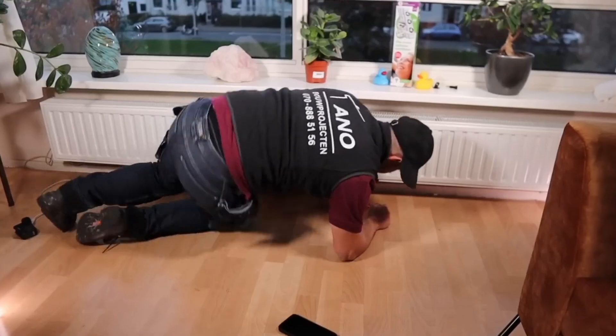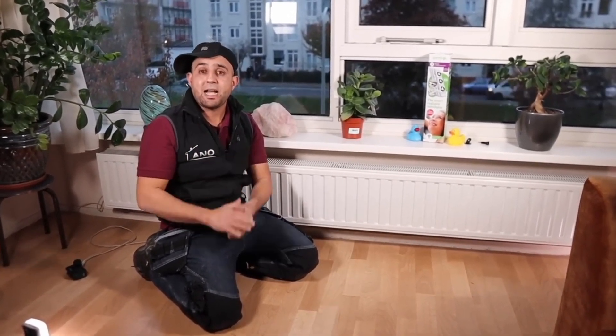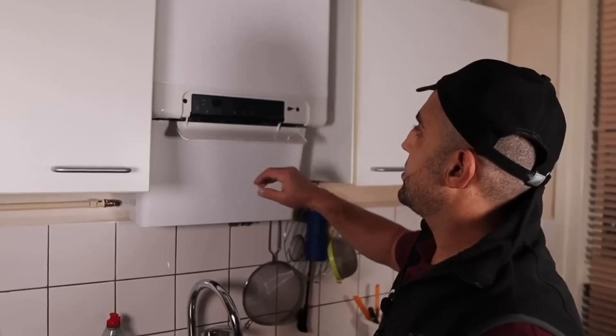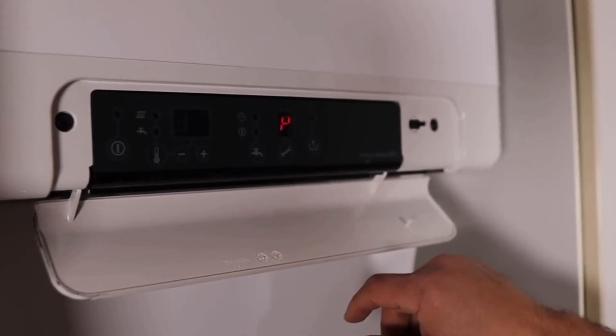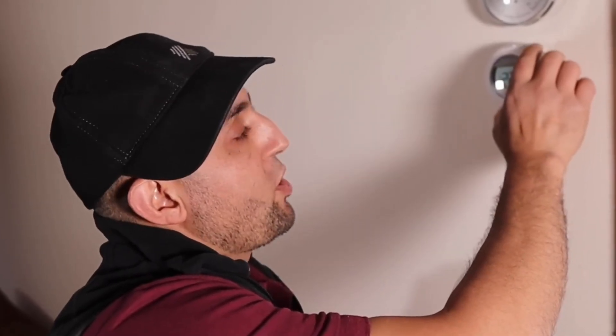Sensor on it — these fans are on. The only thing I have to do now to lower my energy consumption is to lower the temperature of my central heating water. In a standard installation, this is often set between 70 and 90, and I'm now going to lower my radiator temperature to 60. If I can manage with this, then it's perfect. If it's just too tight, I'll raise my temperature to 65 or 70. Then I'll turn up the thermostat to test — I'll just set it to 23 degrees. Now I wait until my radiator is warm enough and the fans should come on at approximately 33 degrees.